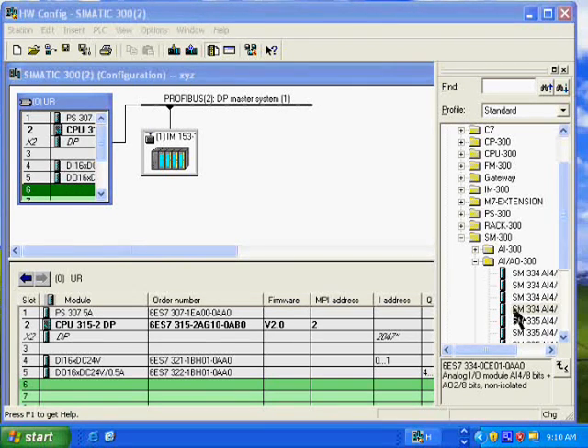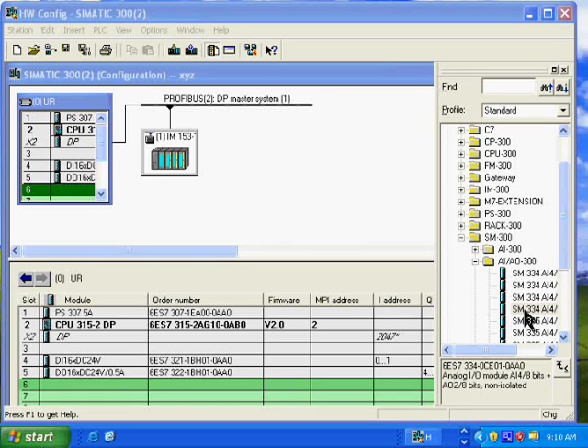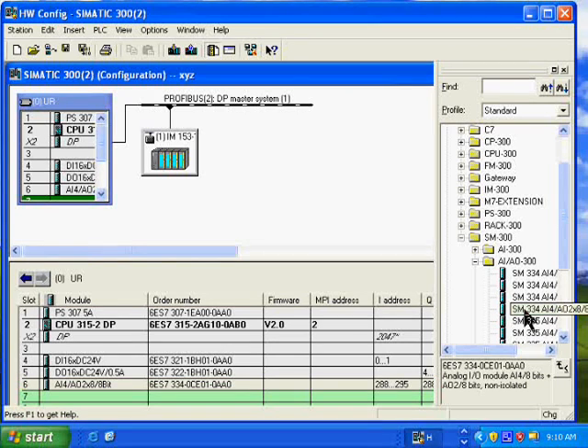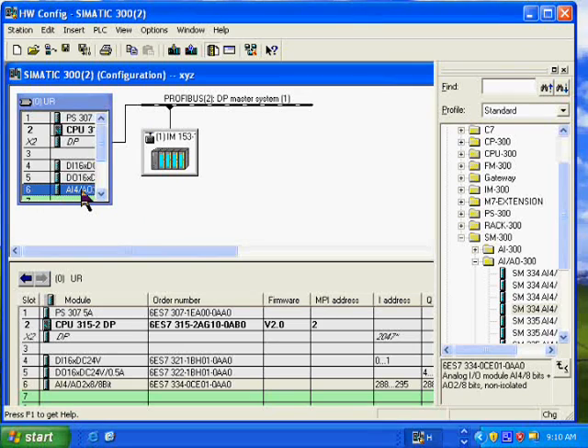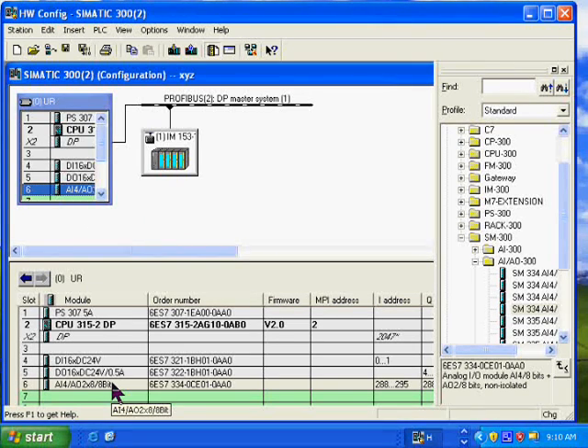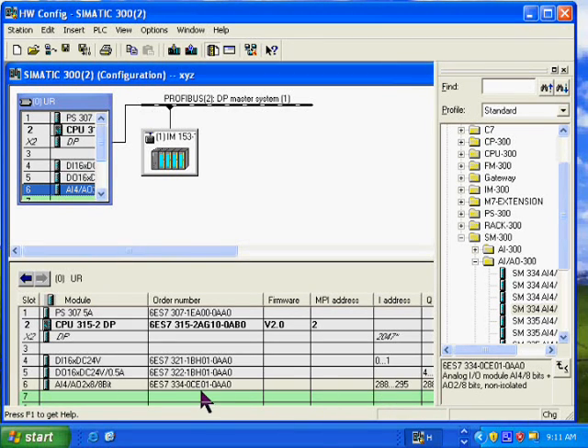In this case, from the right-hand tree, I have selected the analog module that is going to be sitting in slot 6. And if I just double-click that guy with the slot selected, it places the module in the slot, as well as below it give me more information concerning that module, such as the input, output addresses, order number, as well as a small description.